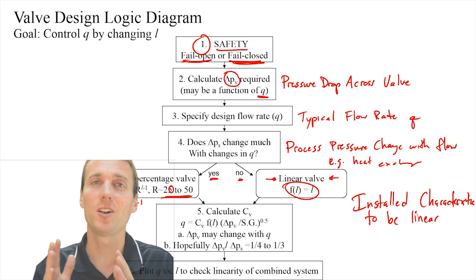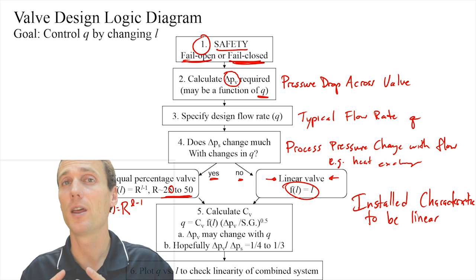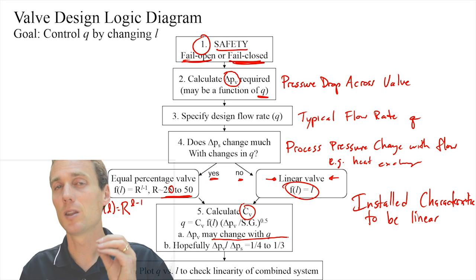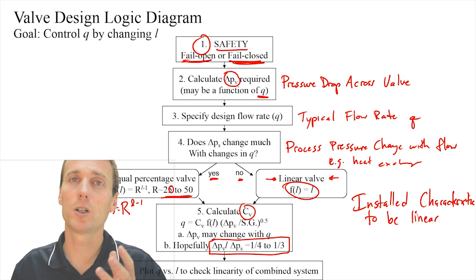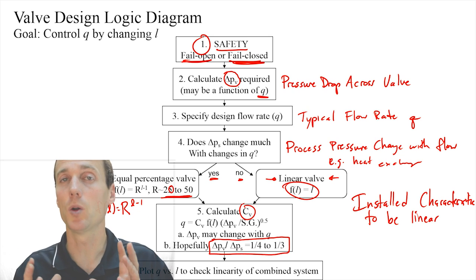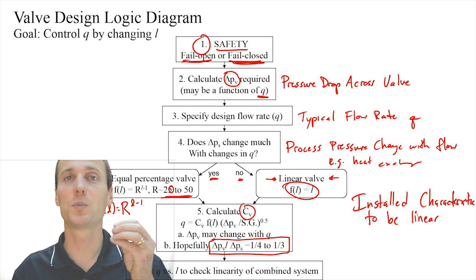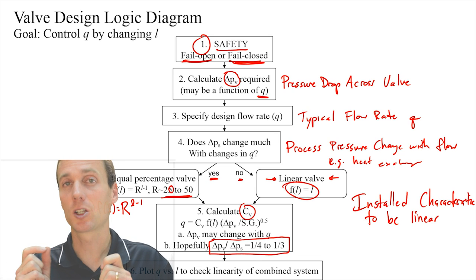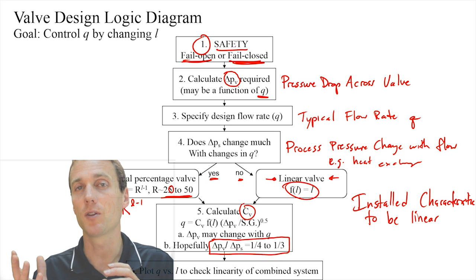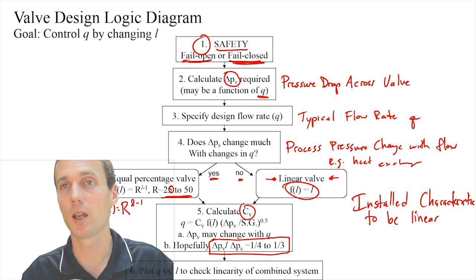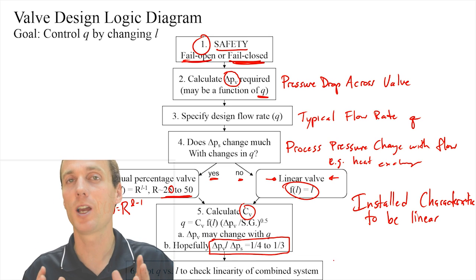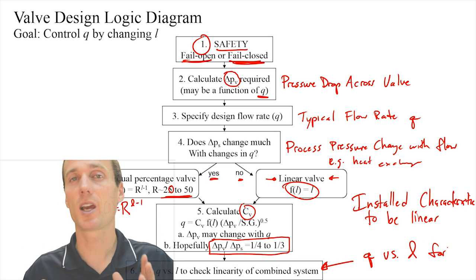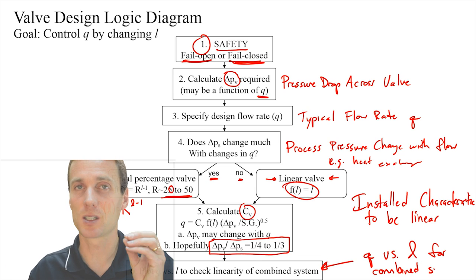If we choose an equal percentage valve, we're going to get a linear response for the valve plus the system. But if the flow rate through the system doesn't really affect the pressure drop, then we can choose a linear valve because then the installed characteristic of both is going to be linear. As a final step, after choosing equal percentage or linear, we want to calculate the CV needed for our particular application. Typically, we want the pressure drop across the valve to be a quarter to a third of the pressure drop across the whole system. We don't want it to be too much because then we have to install larger pumps to compensate. As a final step, we plot Q versus lift L of the combined system to check the linearity of this combined system — the system plus the valve.